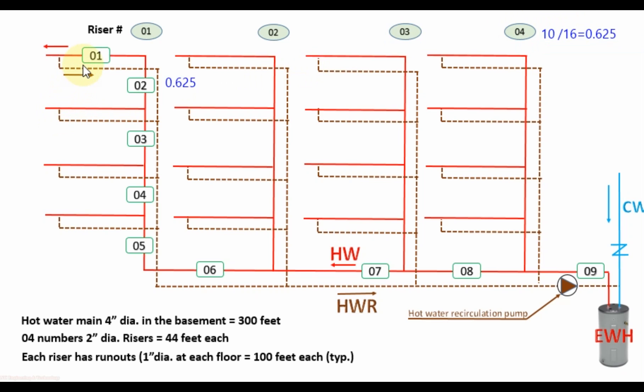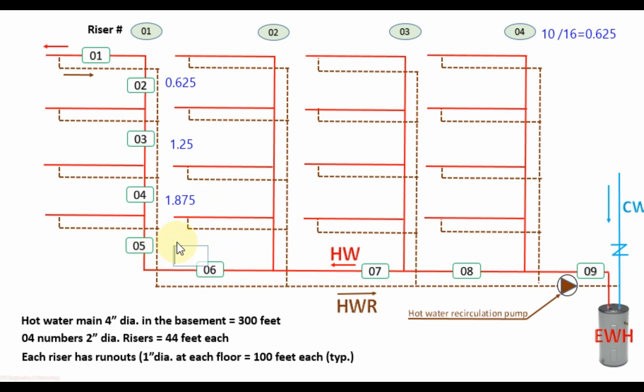For pipe segments 1 and 2, we need 0.625 GPM. For pipe segment 3, there are 2 branches connected before it, so the GPM is 1.25. For pipe segment 4, with 3 branches before it, GPM is 1.875. For pipe segments 5 and 6, with 4 branches before them, the GPM is 2.5.